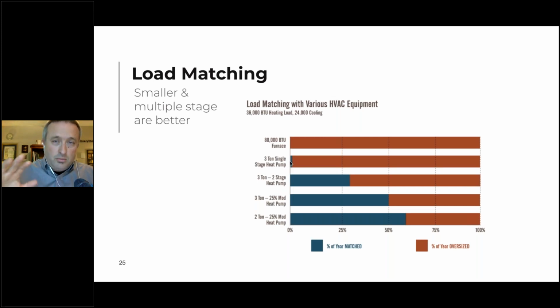So this is squishy. I understand the vagaries of heat pump output, but let's just say they do 36,000 all the time, or view it like a furnace. It's gonna be wrong almost all the time. If we do a 2-stage heat pump, now we can get to maybe 30% of the year where we can come close to matching what the house needs. But if we really want to get there, we need to go to a full modulating piece of equipment, which we're going to come back to again.